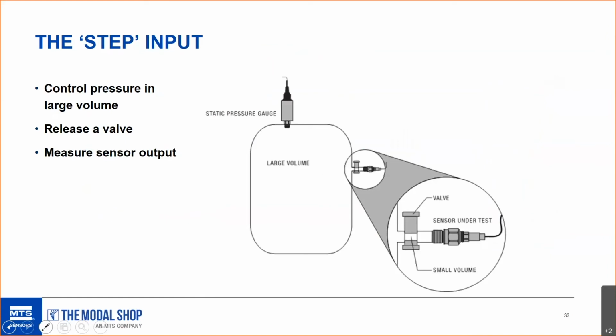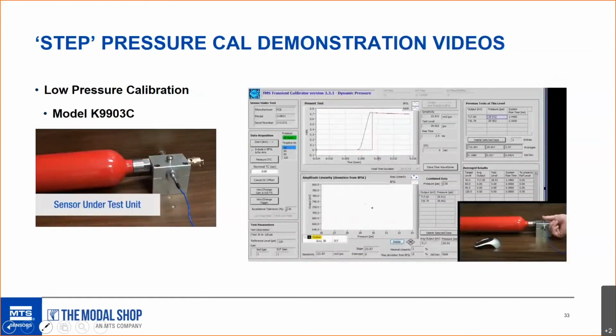So here's a video. We show the data acquisition of the 903 series. This is a little bit of an older model with a red tank on it. Just so you know, this red tank is not the large volume that I mentioned before. It's actually a mechanical filter that we use. And you see that the operator here is opening the valve with the flick of the thumb. Each time he does, he collects another data point, and it's collected in a data table. Then we fast forward to a higher pressure level, and you can see the diagonal line of data that we discussed.